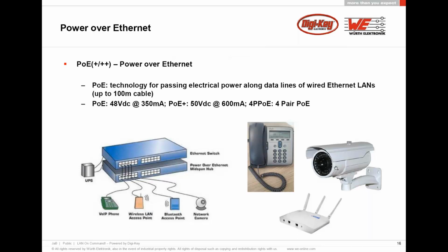If we recall the 100 base T application, where we only use 2 of the 4 pairs of the Ethernet cable, we can have 2 pairs for the data and the other 2 spare pairs for the PoE current, or we can also use the data lines with current. For 1000 base T, we have no possibility of using spare pairs because we use up all 4 pairs. Since 1 or 2 years ago, we have a new standard on the market from IEEE 802.3, the BT standard with 4-pair power over Ethernet, which standardizes how the power should be transferred when we want to use all 4 pairs.